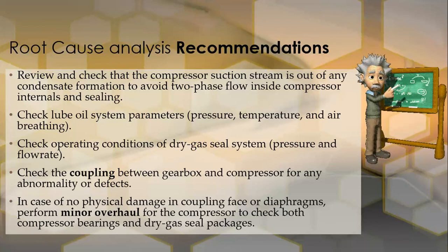We recommended to check the lube oil system parameters, the pressure, temperature, and the air breathing, and an oil analysis sample. And we found that the oil sample was containing water content and it was foamy.